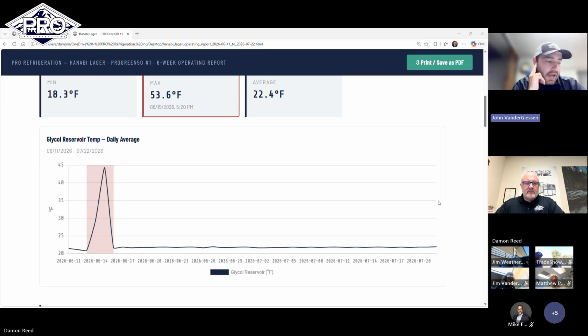So we went out there the next day and did a little evaluation on the unit, and we found that there was a little threaded connection on one of the hose connections that unthreaded itself, and it was leaking there. And it was a big ball of dry ice from that cold liquid coming out of it. So it was pretty easy to spot, just seeing the big ball of ice. We got it tightened up and recharged, and it was back off to the races. So that's why we have that glycol temperature spike there: the chiller was down for those days.